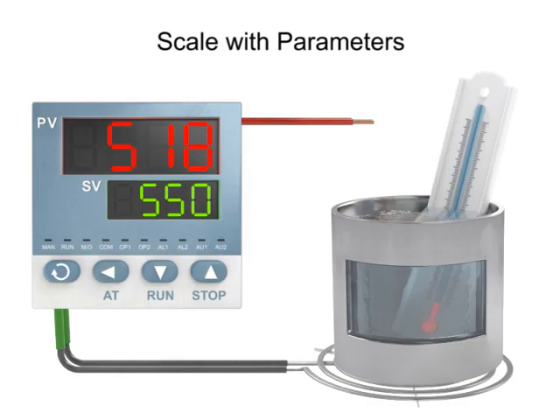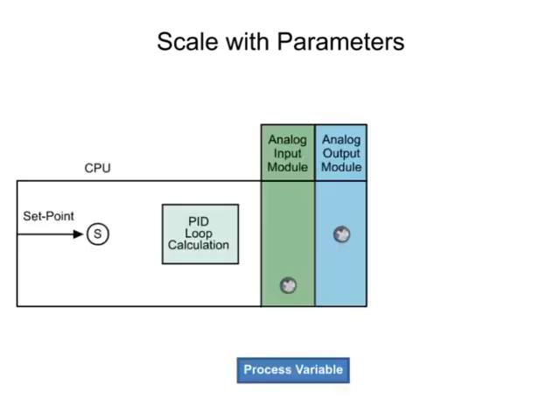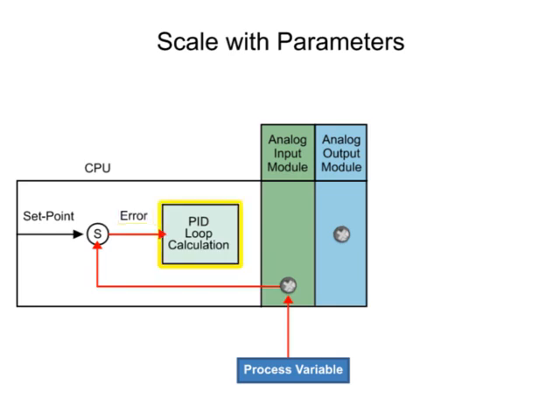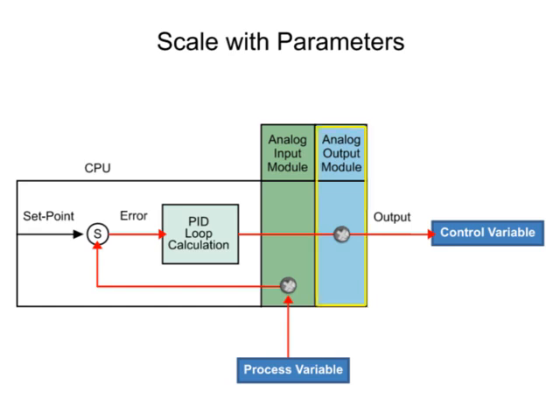PID control is a common closed-loop system used to maintain physical properties such as pressure and temperature in automated processes. The PID instruction controls the closed-loop by comparing the input or process variable from an analog input module to the system set point. The difference between the set point and the process variable is referred to as error. The error is analyzed by the PID loop calculation and provides an output or control variable to an analog output module to meet the set point defined by the system requirements.